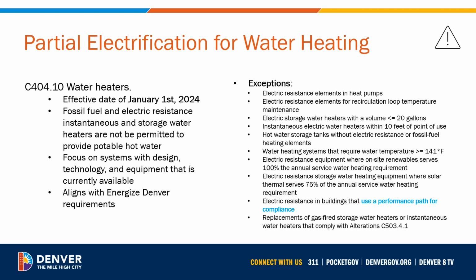There are many circumstances where exemptions may apply, with a few notable ones being electric resistance is allowed in certain small or point-of-use water heaters, electric resistance elements in heat pumps or recirculation loop temperature maintenance, high-temperature water heating systems, and that a project may utilize electric resistance water heating if a performance compliance path is pursued.